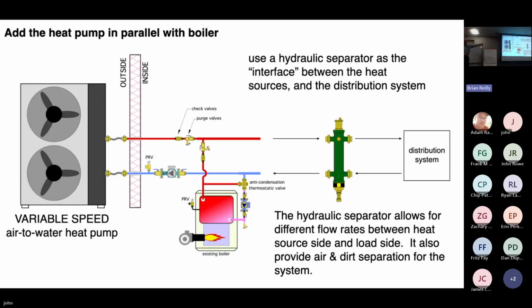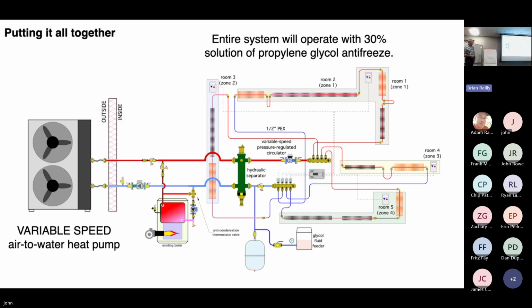Two more slides here. So I've added the heat pump, connected in parallel with the boiler, same piping details. I'm going to put a hydraulic separator in. It's going to do air separation, dirt separation, and it's going to separate the pressure dynamics of these circulators over here from whatever this distribution system is. So there it is put together.